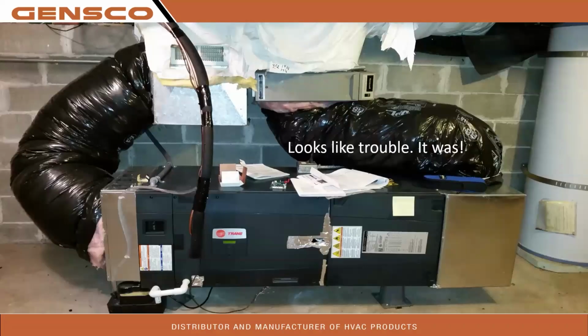It's an actual install. Mark was on site where they were having some airflow issues. Actually, I went back on site on this one too. They definitely had to correct everything, move this around, reposition the air cleaner right here. Again, when we're connecting to air cleaners, we have to have some kind of transition to utilize every square inch of that surface area for that EAC. And we'll go a little bit, I'll show you some graphs for the AccuClean filters and the Clean Effects. So they had to remedy that airflow because it was having constant issues.